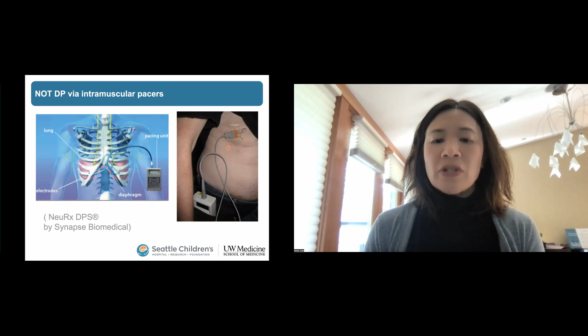The benefits with diaphragmatic pacing are that for some, it allows for decannulation, but for a surprising amount, it does not. And that's something really important to keep in mind. The newer transmitter, the Spirit, has a disconnect alarm. It is very portable. It is non-intrusive. Challenges include this lack of ability to figure out if your upper airway is going to handle it without a tracheostomy or not. It does require surgery and general anesthesia for placement. You can only do it up to 16 hours a day. And you still, in my mind, need to have BiPAP available in the house in case those transmitters fail. You need to have a backup plan.